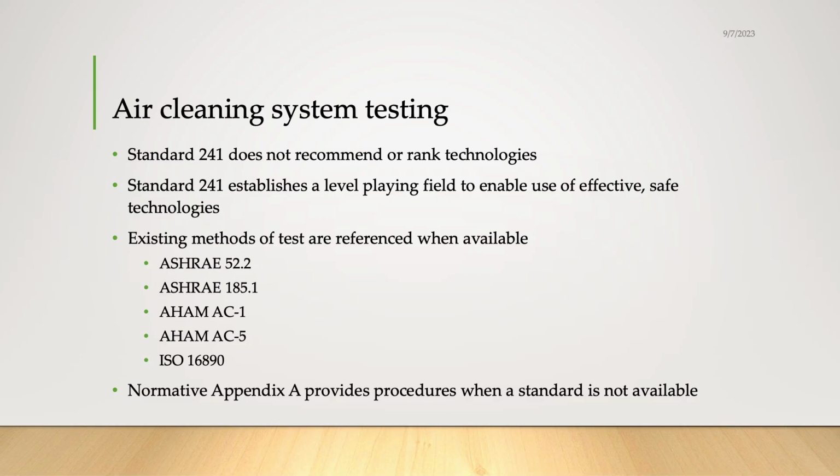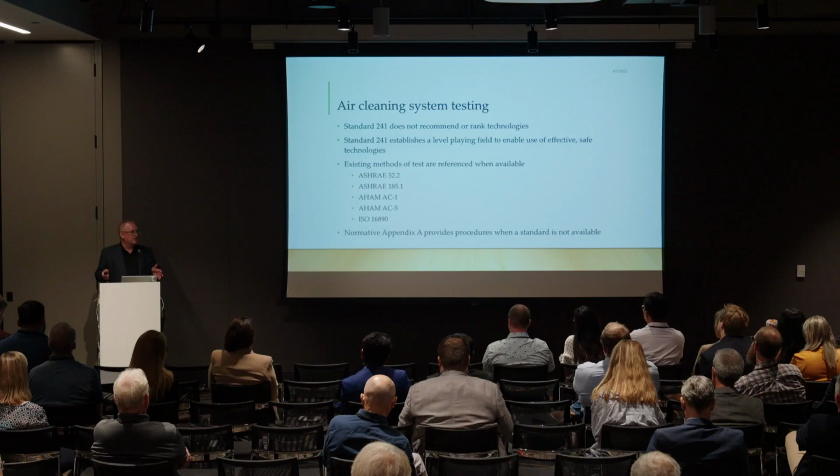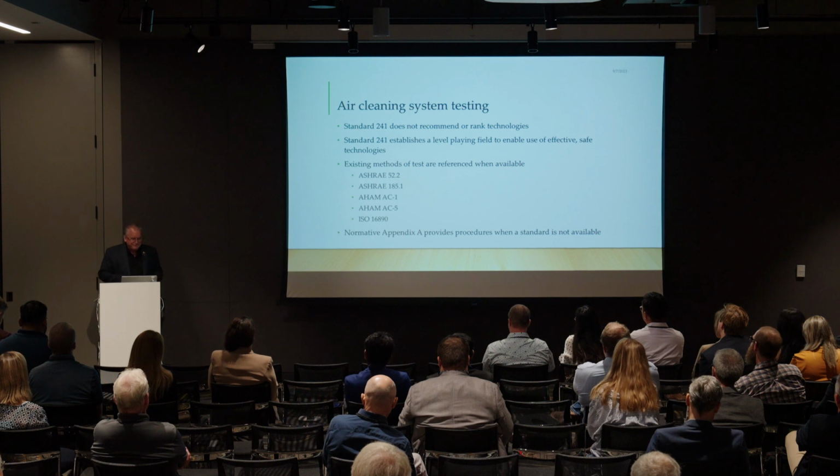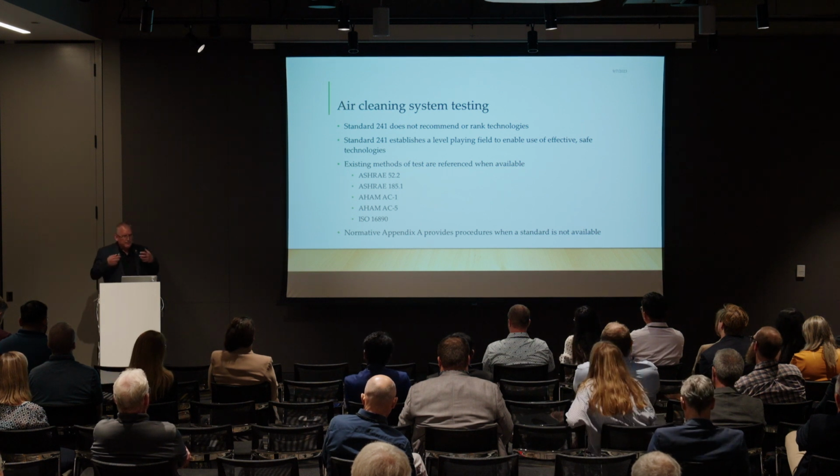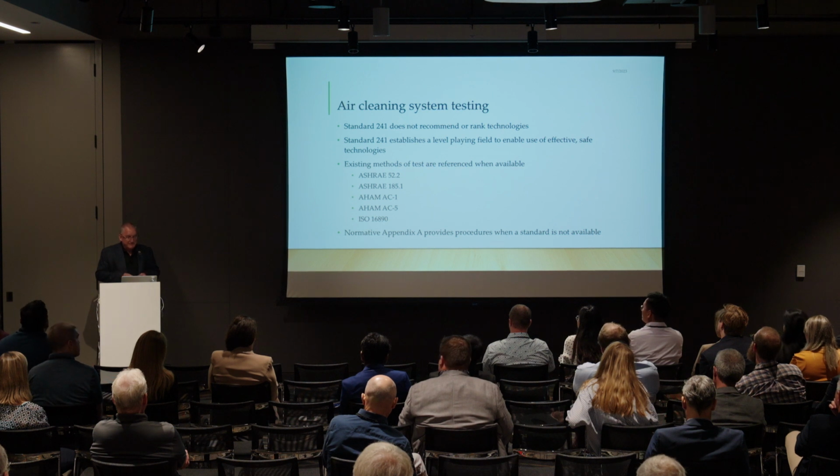So there's a big appendix on air cleaner testing, and whatever your technology is, if it is characterized according to the effectiveness criteria and passes the safety criteria, then you can use it. We don't rank technologies. We don't promote certain technologies. The goal here was to be technology agnostic and create a level playing field that had appropriate requirements for qualifying the use of these technologies.